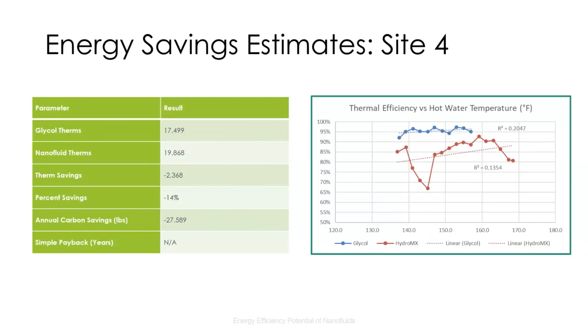As you can see, the boiler efficiency on the chart at the right does increase with higher temperatures in the nanofluid case, which isn't the typical performance for condensing boilers. And also there's not really a good explanation for the dip in efficiencies as shown in the red line. The average estimated efficiency across the operating range in the nanofluid case is approximately 87%, which is less than we expected. And lastly, as shown by the lines on the chart, the boiler operated at higher supply water temperatures in the proposed case, and operating at different water temperatures can affect the performance of the boiler as well.